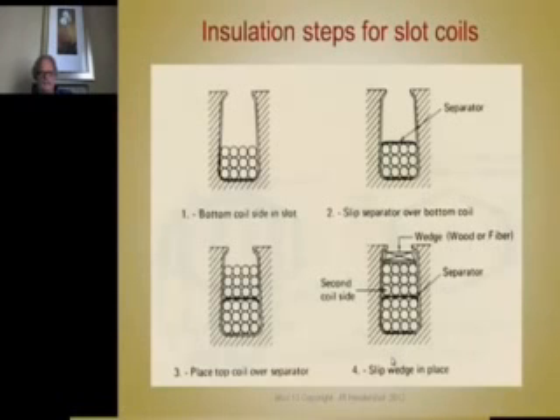This shows the steps of insertion and insulation. This would be a random wound slot with quite a big slot opening here. So you put the slot liner in. You put one side of the first coil in. These are lap windings, where one side of the coil goes in the bottom of the slot. Then so many teeth later, according to the span of the coil, depending on the number of poles, the other side of the coil goes in the top of the slot. So these overlap like this.